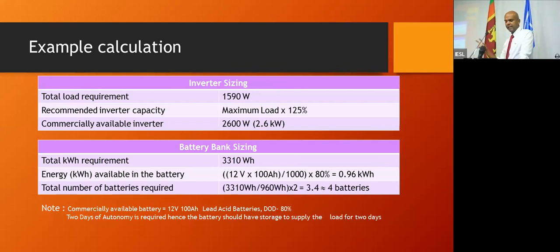In this case I've used 80% as the depth of discharge. No, you can't, don't use 80%. If you're using a lead acid or AGM battery, use 50%. 80% I put if you are rich enough to buy a lithium ion battery, you can discharge it to, they say 100%, but I think 80% you can. So typically, if you have a car battery, for God's sake don't discharge it more than 50%, you're going to kill the battery very, very soon.